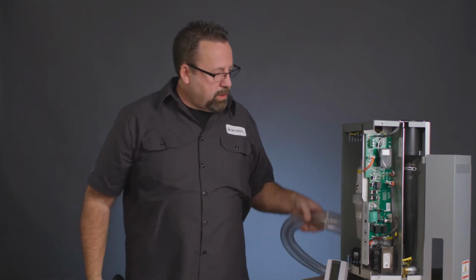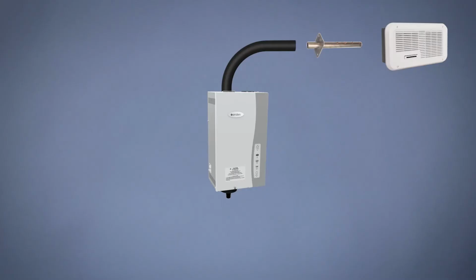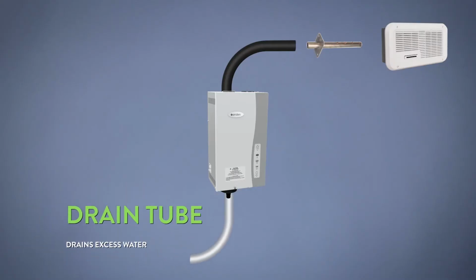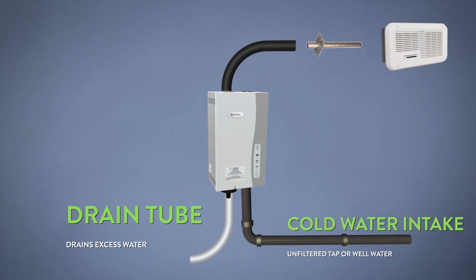The humidifier also comes with 10 feet of drain tubing. The drain tubing connects to the bottom of the unit. The unit is using cold, normal tap water, not reverse osmosis or deionization process of any type of water, just plain water, cold water, so that when the unit drains, it would never exceed 140 degrees, 160 max.